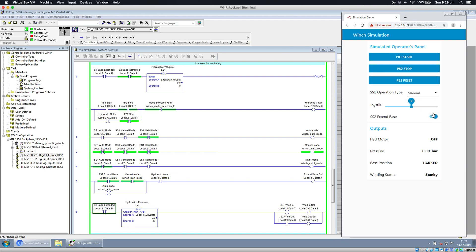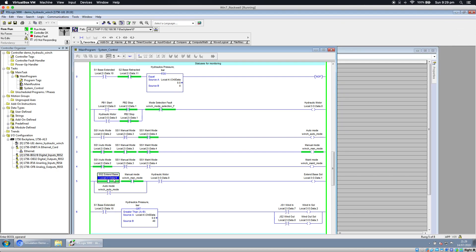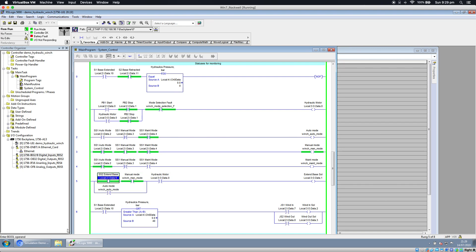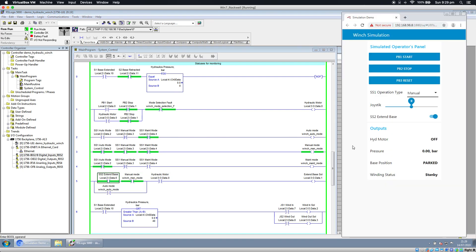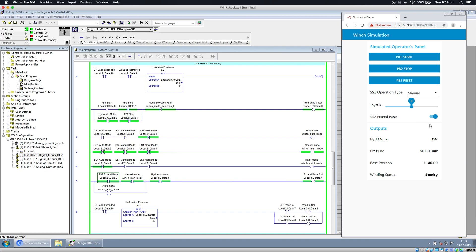Now, extension doesn't work either because extension base input number six is waiting for manual mode and waiting for the hydraulic pump to be on, which is not on right now. I can leave it on extended base, select the switch, and start the pump. When pressure reaches the limit, the base extends automatically. We can stop it at any time and it goes back.